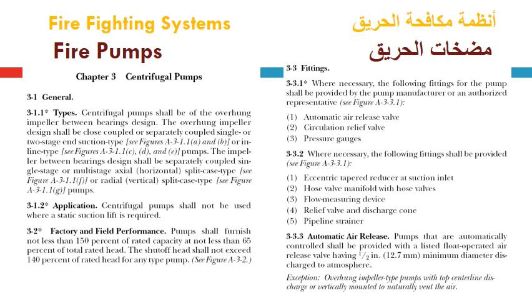Fittings. Where necessary, the following fittings for the pump shall be provided by the pump manufacturer or an authorized representative. 1. Automatic air release valve to prevent air from accumulating in the water passage inside the piping system and the pump. 2. Circulation relief valve to protect the pump and the discharge line from any maximum pressure expected due to shutting down of the system components on the discharge line. 3. Pressure gauges to read and monitor the pressure on both the suction side and the discharge side. Where necessary, the following fittings also shall be provided.